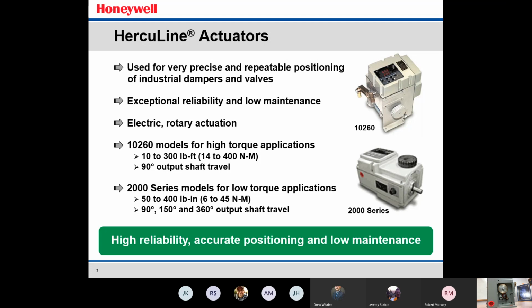The nice thing with that auto/manual switch is that if you're on a new startup or installation and you need to stroke the valve out at the valve to position the linkage that you're setting up on it, it's very easy to use that auto/manual switch to ramp the actuator up, set the linkage at the high end, ramp it all the way down with the manual switch to set your linkage at the low end, and instead of going back and forth to the controller or the control loop to put the control loop in manual, you could do it right at the actuator. Saves a lot of time doing startups.